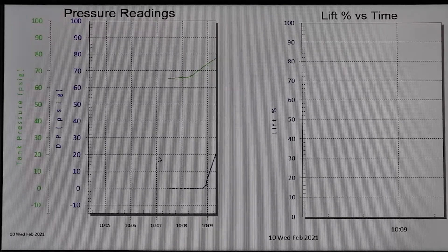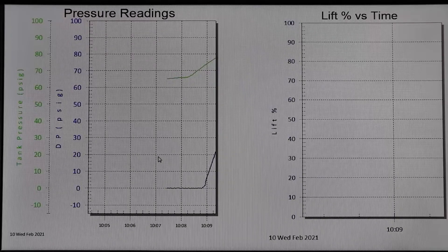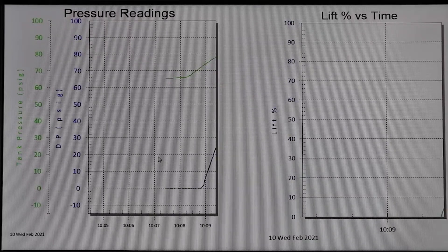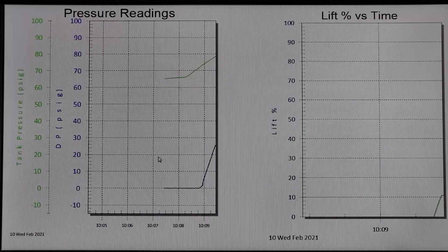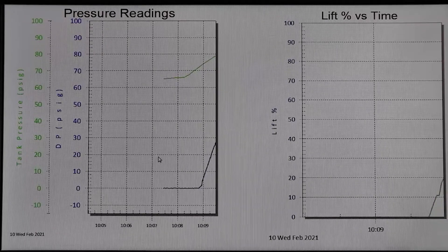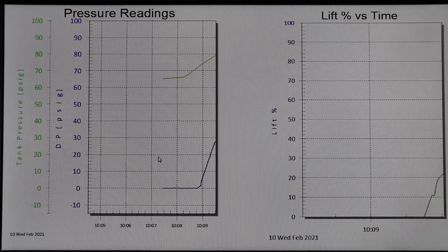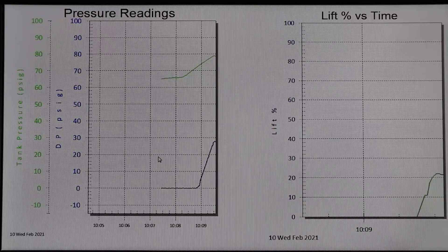On the vertical axis you will see the system pressure shown in green and the differential pressure reading of the valve's dome to inlet in blue. The right graph shows the percentage of the valve's lift over time and is calculated based upon the valve size and differential pressure.